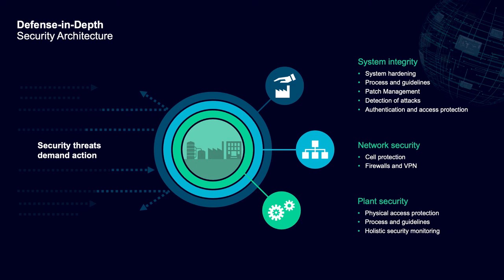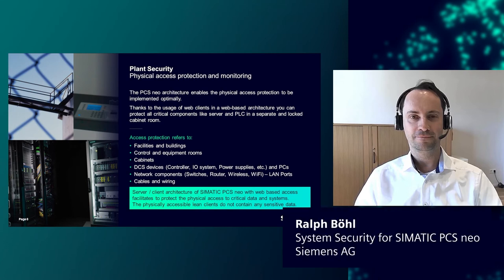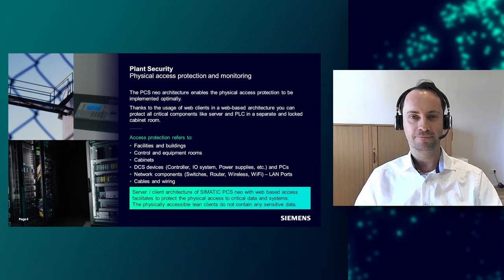That means, for example, that only the necessary functions are installed, users and applications have only as many rights as they require for their tasks, and the functions required for the system are securely pre-configured. Regarding the web-based control system, the architecture of SIMATIC PCS neo makes it possible to implement physical access protection in the best possible way. Thanks to the web-based architecture, you can protect all critical components like servers and PLCs in a separate cabinet room, whereas the web clients do not contain any critical data. These security concepts are applicable whether you make the system remote-accessible or in a closed-network environment.